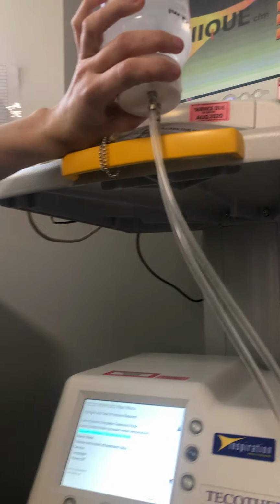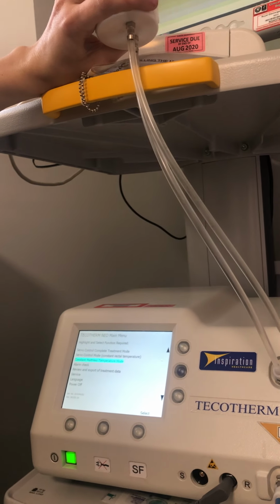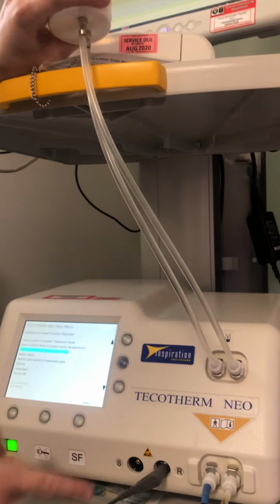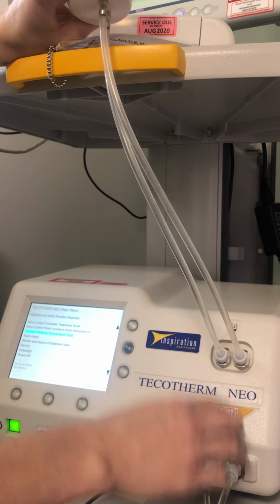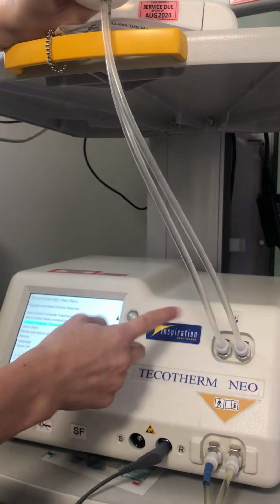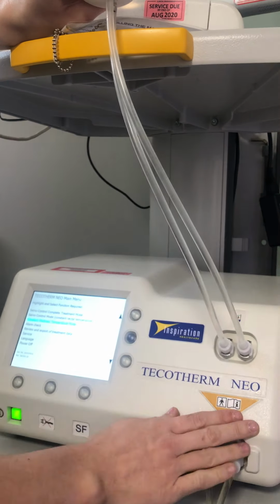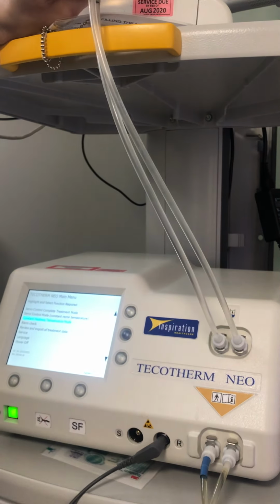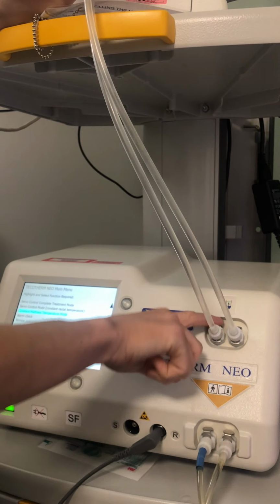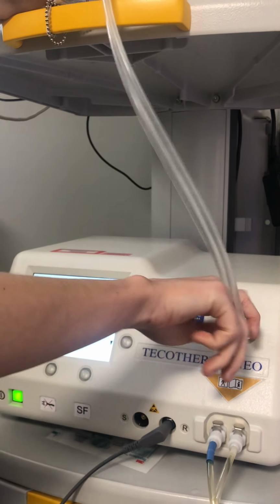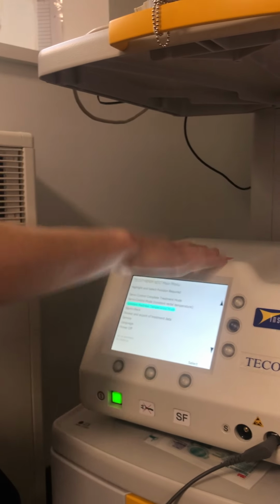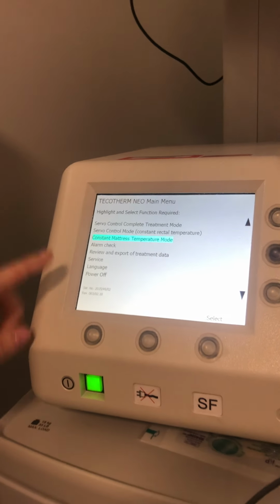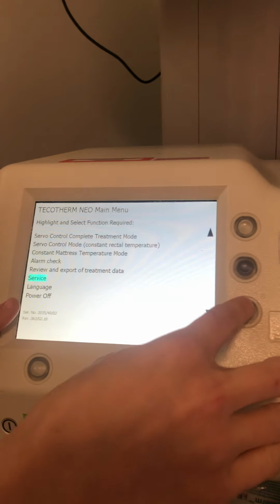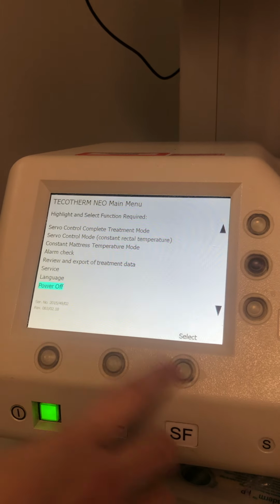We should be leaving the mattress filled with sterile water. So you need to use the cleaning fluid to clean it first, using that method with the mattress on the top and the bottle emptying. Fill it with the cleaning fluid like we would now, bottle on the top, fill it, re-empty so the cleaning fluid is out, and then refill it with the sterile water. Once you're happy it's filled, click them both off and leave the mattress on the top. To switch the machine off, the green button doesn't do anything, it's a safety feature. You actually have to go all the way down to power off and select. And that's it. That's how you set up the cooling mattress.